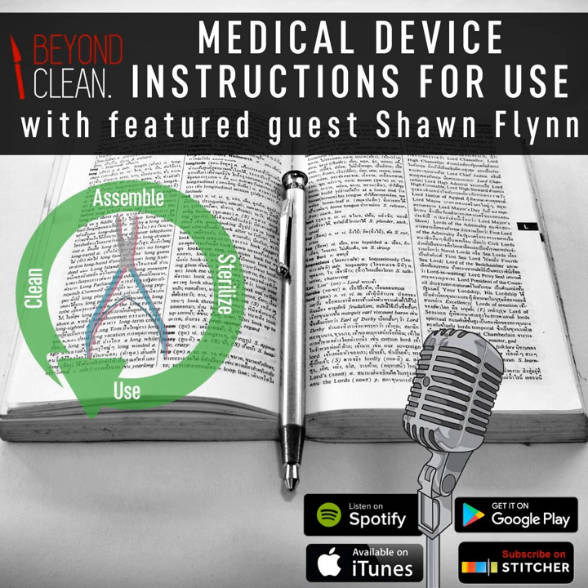Or even the rationale behind why they listed something. The interesting thing about a manufacturer's IFU is that their main goal is to pass their validation test. So when you see IFUs that are very intricate in nature, they're derived with that in mind, as well as to mitigate risk for their risk hazard analysis or FMEA, failure mode effects analysis.